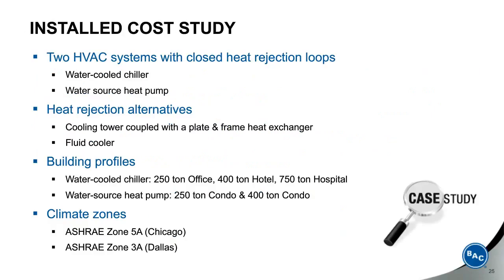IMEG looked at two closed-loop HVAC systems for us, a water-cooled chiller and a water source heat pump, using two alternatives: a cooling tower coupled with a plate and frame heat exchanger, and a fluid cooler. Both options were evaluated in differing building types with different heat loads across two ASHRAE climate zones, using the major cities of Chicago and Dallas, which exhibit markedly different climates.